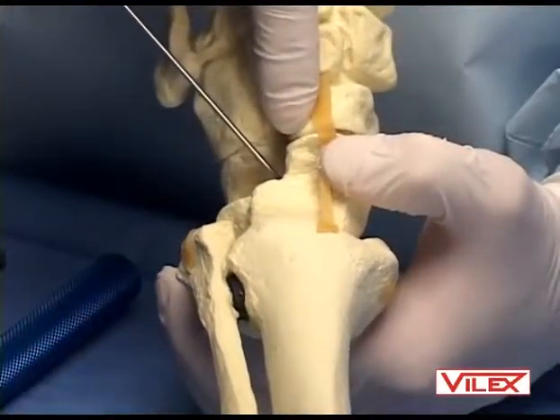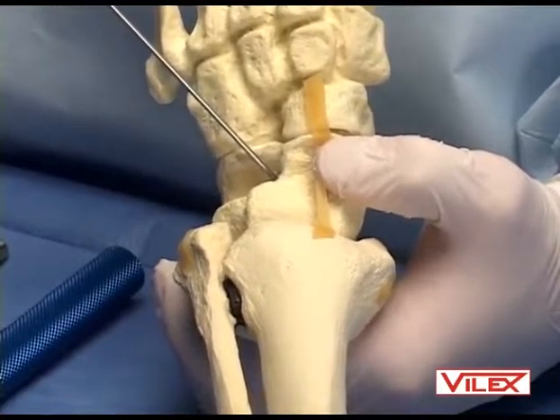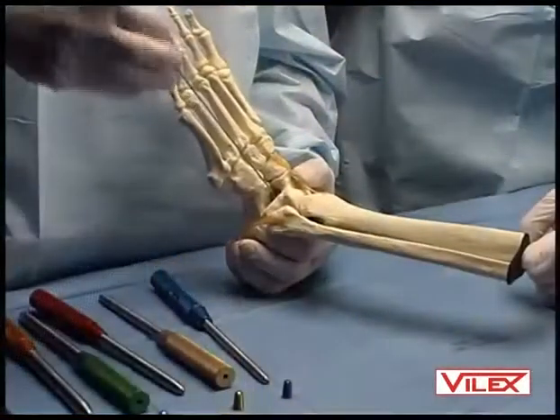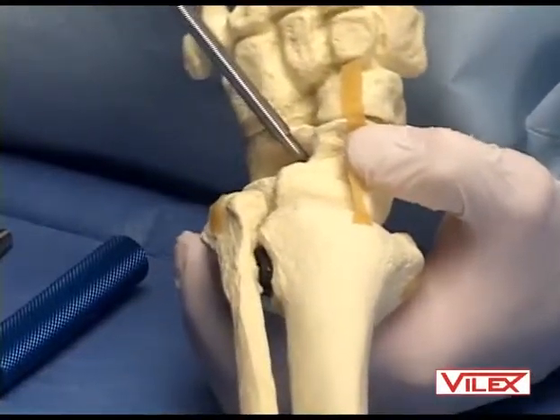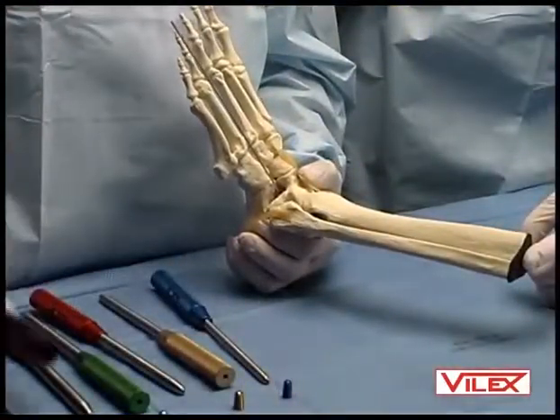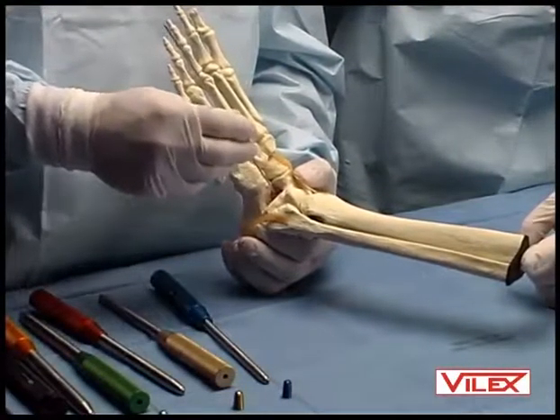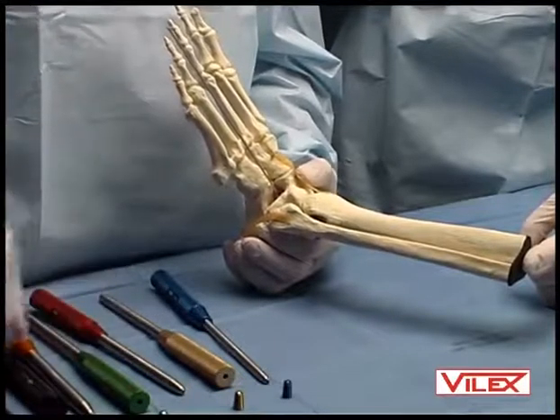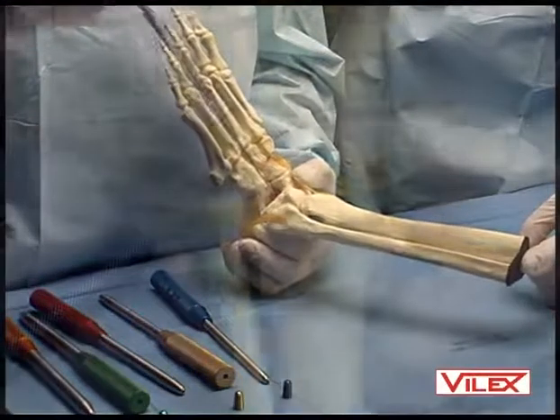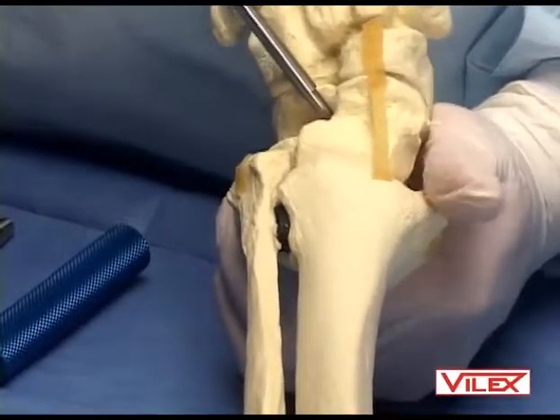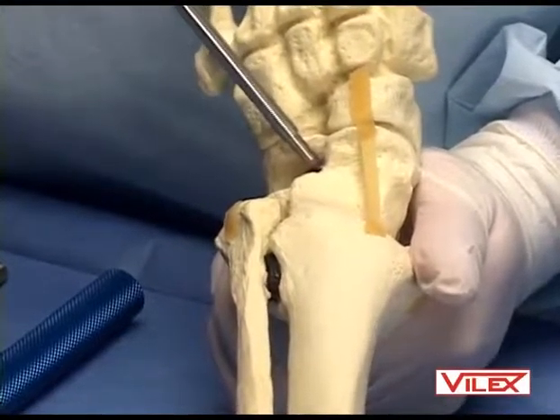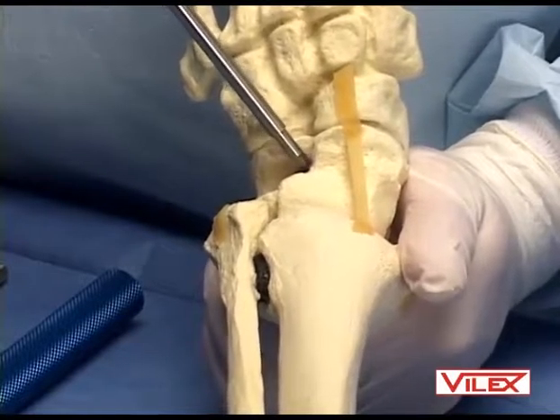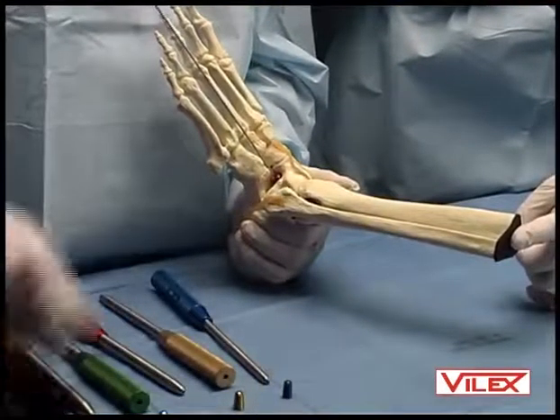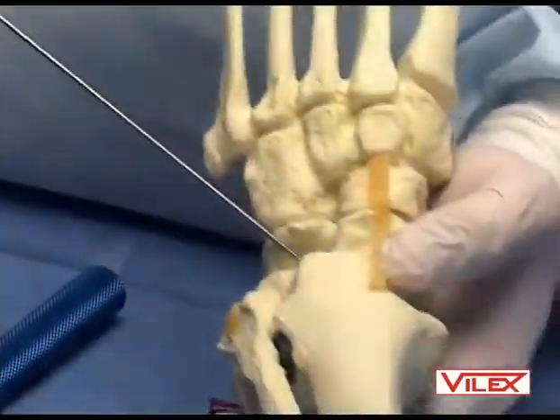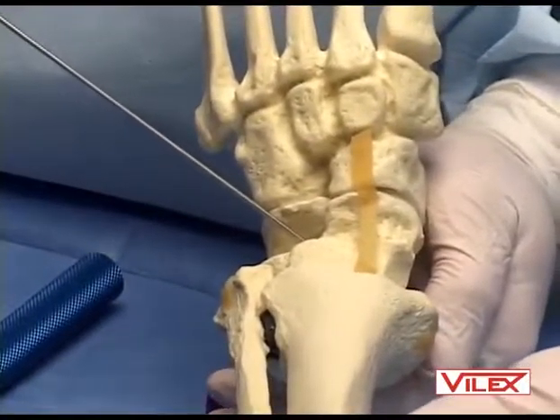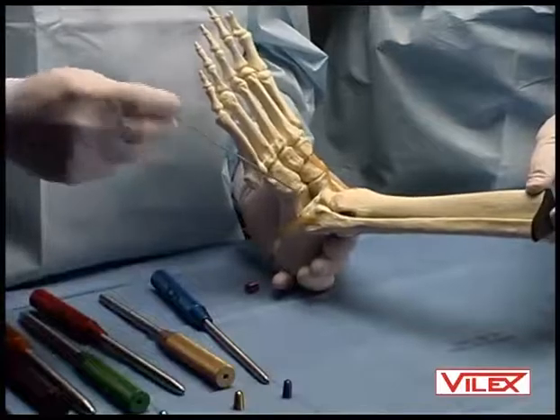And if you're not at the bisection of the talus, you can advance it further. Just take the screwdriver, pass it back on, and advance it a little bit further. If you feel that you're advancing it too far, the better thing to do, rather than advance it too far, is to take this implant out and go to a larger size. Since you still have that guide wire in there, it makes it easy to do all this, passing it back and forth on the actual implant. And then what we'll do is pass to the next size up and advance it.